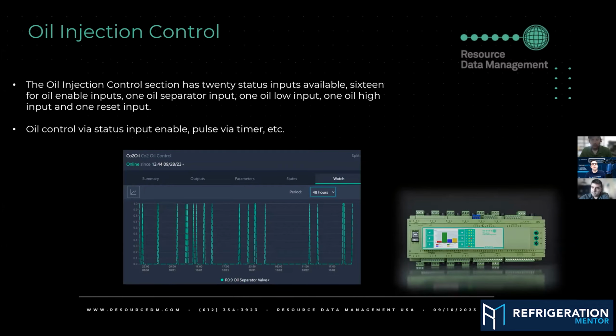How often do you guys see using oil injection control? Because there's many different designs. There's oil with solenoids. There's oil with high pressure oil in with the oil level controller. So when you say oil injection control, what is this controlling, and what type of oil management system would it be? It's Trevor, it's a pulse valve is what normally we're seeing right now.